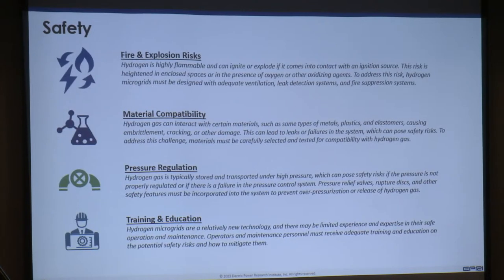So a little bit about safety. Hydrogen is explosive, highly flammable, and it can ignite or explode if it comes into contact with an ignition source. To address this risk, consider designing your microgrid with adequate ventilation, leak detection systems, and fire suppression systems. There are also material compatibility issues with hydrogen, as it can interact with certain materials. There's a lot of work being done in the R&D space on materials and their interactions with hydrogen, so you need to take those into consideration and carefully select materials that are appropriate for your application.